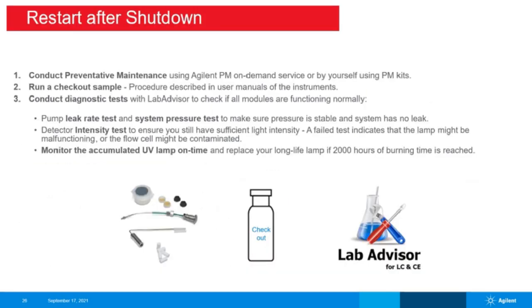Restart the system. Restarting a system after a longer shutdown can become a nightmare. To avoid such a critical situation, a step-by-step approach can help to overcome these different barriers. Step 1. Conduct a preventive maintenance. Step 2. Run a checkout sample. Step 3. Conduct diagnostic tests to check the system wellness. As diagnostic tests, we recommend a pump leak test, a system pressure test, a detector intensity test, and also very helpful is to monitor the accumulated UV lamp on time.